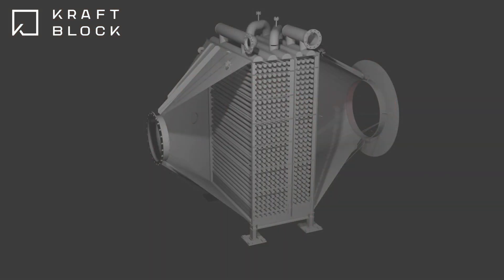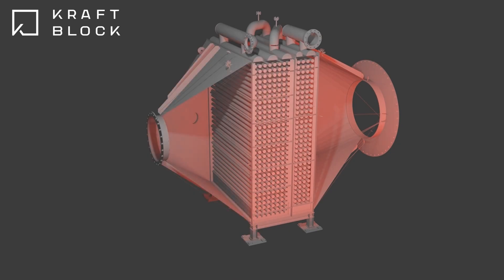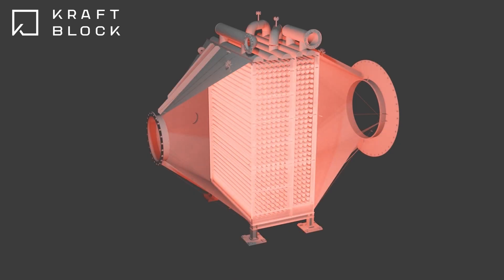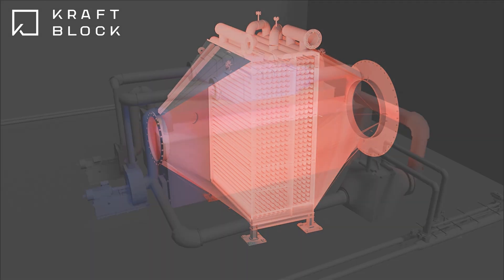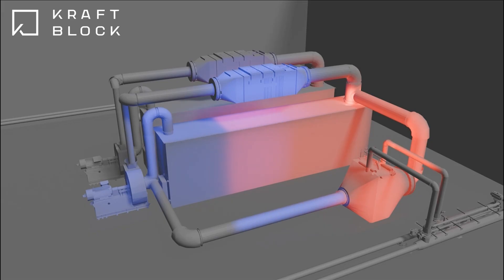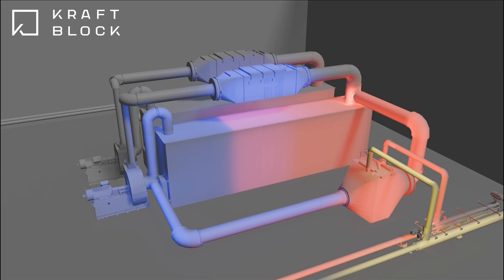Thermal oil has to be heated to heat the frying oil of PepsiCo snack plant. A heat exchanger transfers heat from air to thermal oil at the right temperature. The hot thermal oil is pumped to the frying process. It comes back with remaining heat and is heated to process temperature again, thus losing close to no energy. And this is how the net zero heat system provides clean energy from cheap electricity.